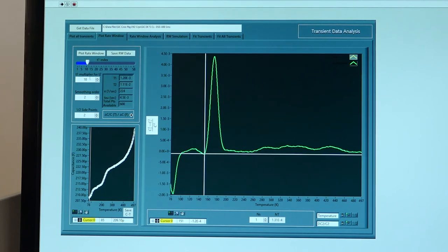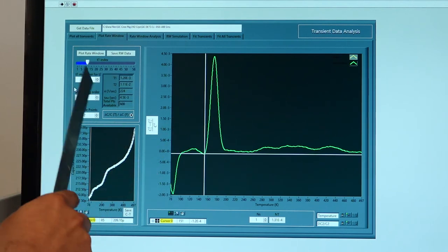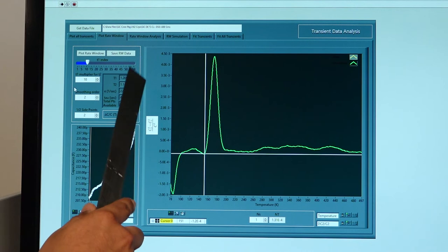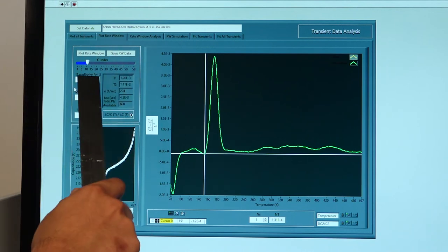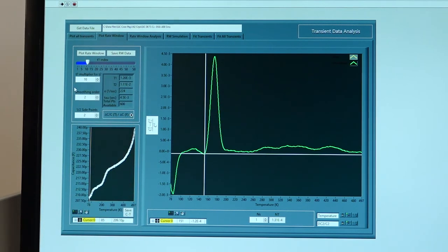We have to now also determine what will be the value of T2. Generally, T2 by T1 ratio is kept constant to generate a good Arrhenius plot. Although other relationships can also be taken, but here we are following the rule where T2 by T1 is a constant ratio. You can select this ratio by this tab, which is showing the T1 multiplier for T2. That means T2 by T1 would be 10. So we have selected the two sampling points, T1 comma T2 now.